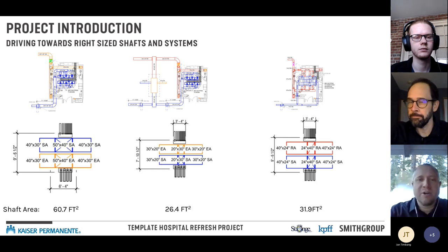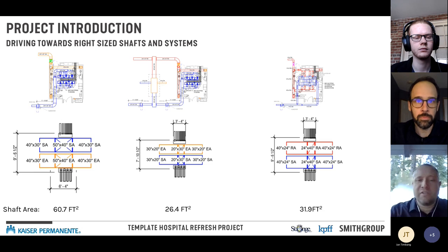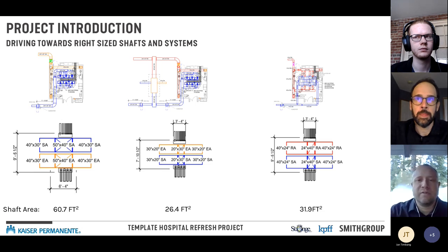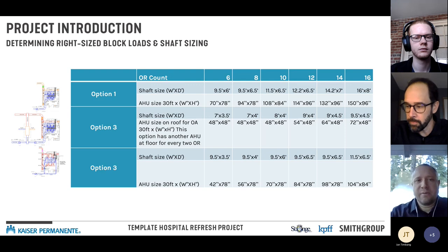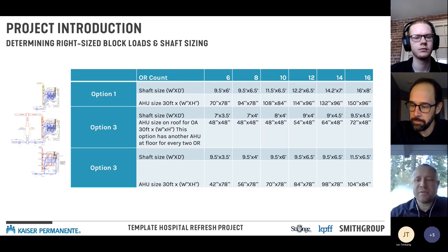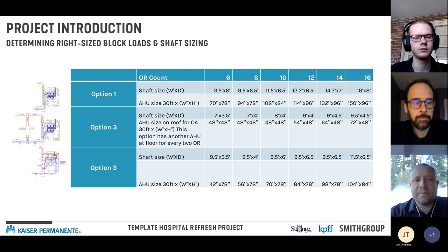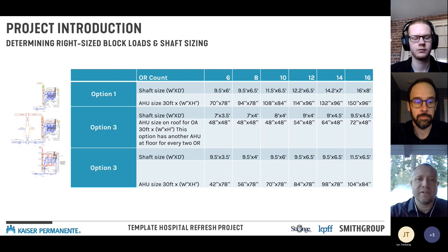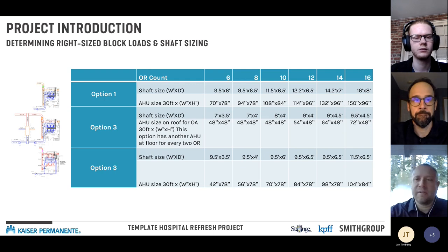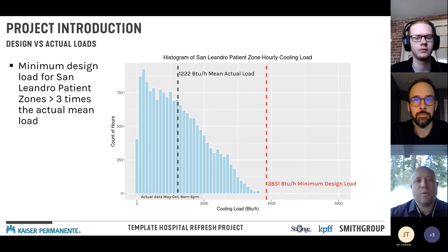Travis and the Kaiser team posed the question: what are the real loads we should be designing for, as opposed to just using off-the-shelf ASHRAE design calculations? That sparked a transition from looking at design calcs toward looking at historic data. One of the big questions was: as we stack up the number of rooms, what's the real level of diversity we can apply to upstream systems, all the way to the chiller plant, boiler plant, shaft sizing, and air handlers?